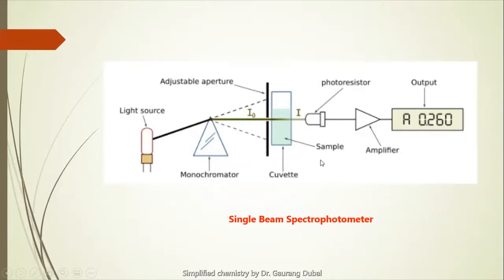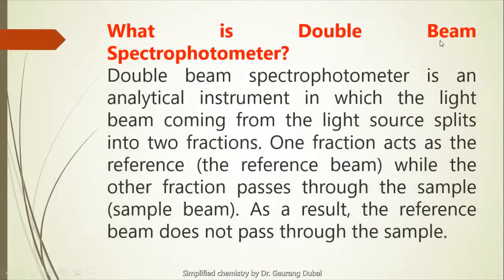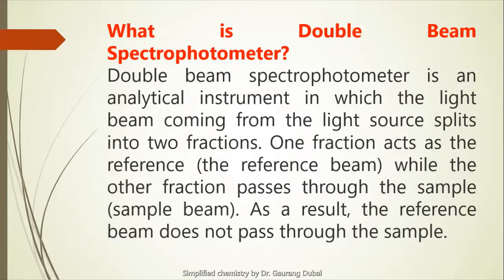Next, what is a double beam spectrophotometer? A double beam spectrophotometer is an analytical instrument in which the light beam coming from the light source splits into two fractions. One fraction acts as the reference beam and another performs as the sample beam, because it passes through the sample while the first one is only a reference beam without sample. As a result, the reference beam does not pass through the sample.